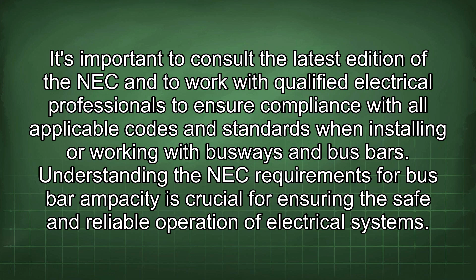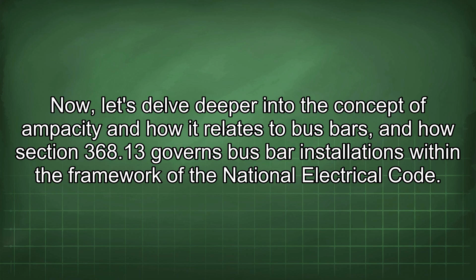Now, let's delve deeper into the concept of ampacity and how it relates to bus bars, and how section 368.13 governs bus bar installations within the framework of the National Electrical Code. Ampacity, at its core, represents the maximum amount of electrical current, measured in amps, that a conductor, such as a bus bar, can carry continuously without exceeding its temperature rating.